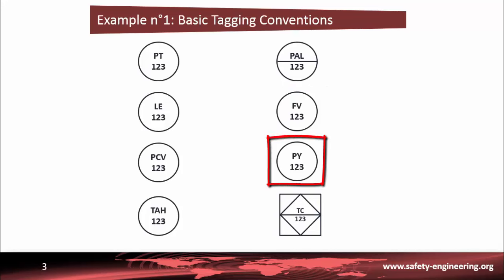PY means a converter or transducer, probably an I/P transducer close to the valve, no line inside the circle, to convert electrical signal to pneumatic signal. Finally, TC means a controller to regulate the temperature. This controller is a programmable logic controller, a PLC, because the symbol is a diamond within the square. This PLC is located on the main control panel.